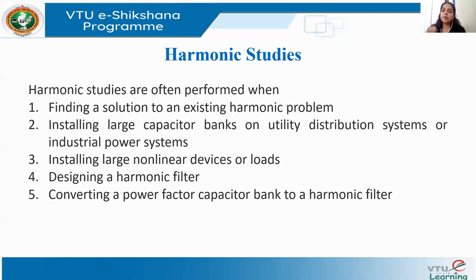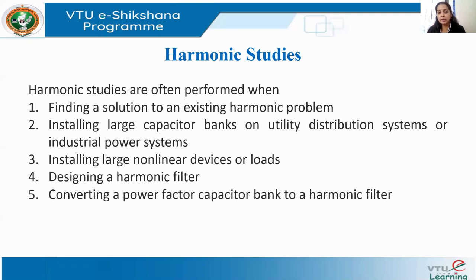Harmonic studies are also required when designing a harmonic filter — before installing it, we need to study its effect. Another case is when converting a capacitor bank to a harmonic filter, since the capacitor bank can itself act as a filter. Basically, harmonic studies provide a means to evaluate various problems and possible solutions, and to find their effectiveness under a wide range of conditions.